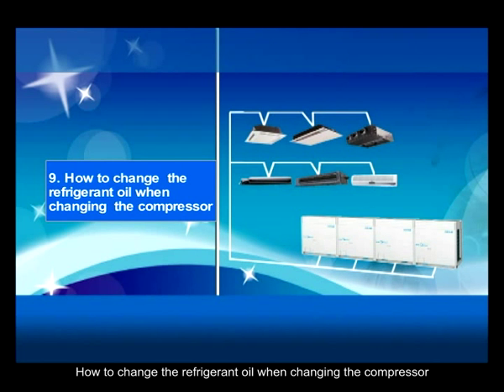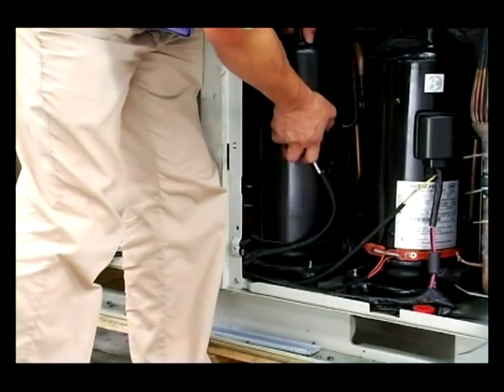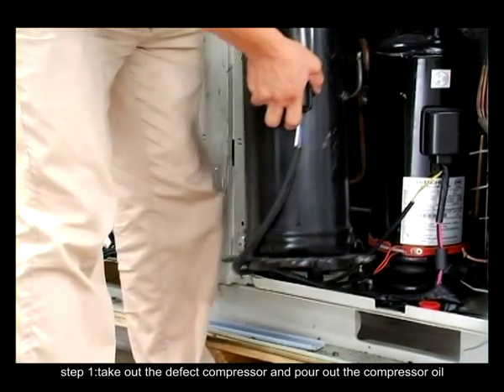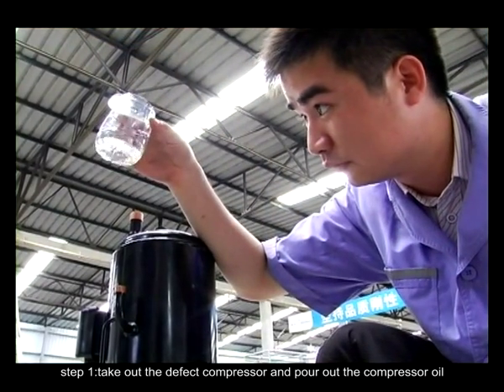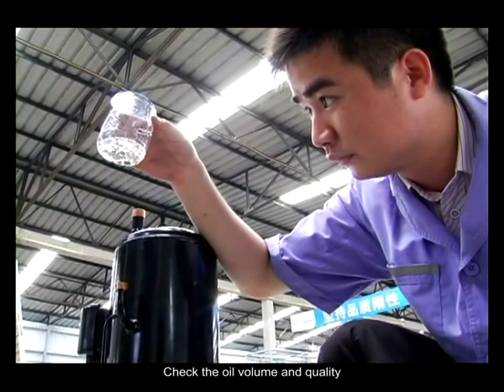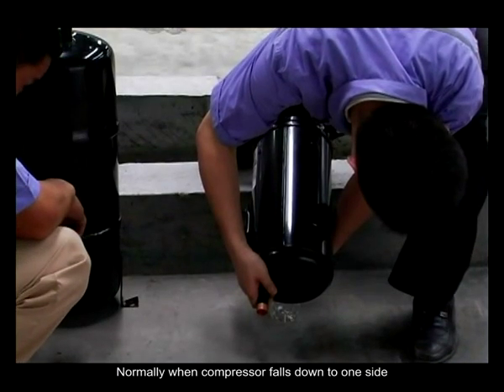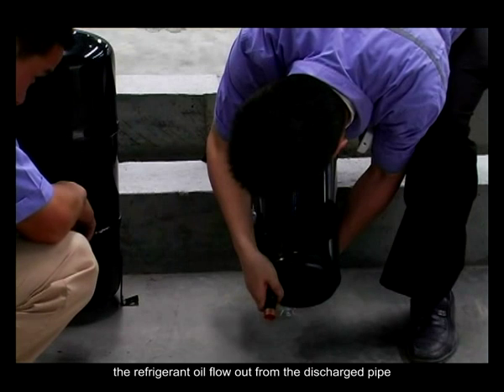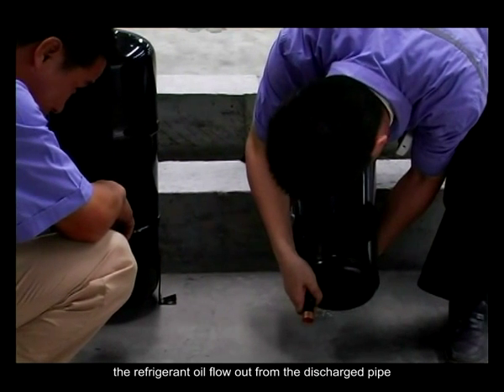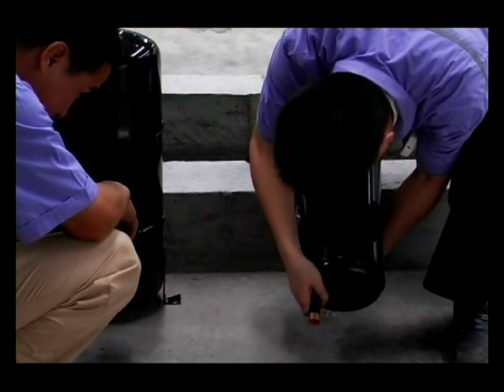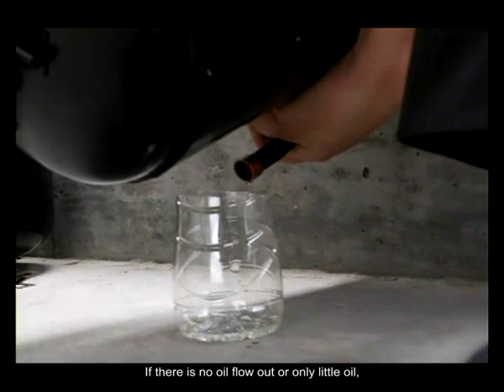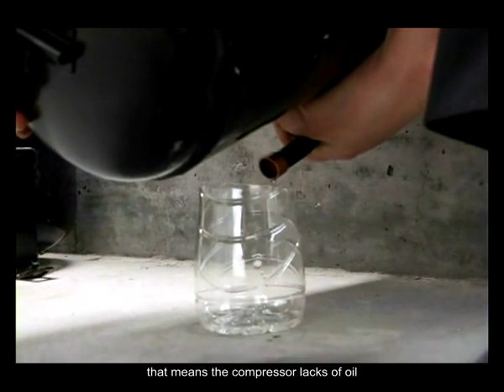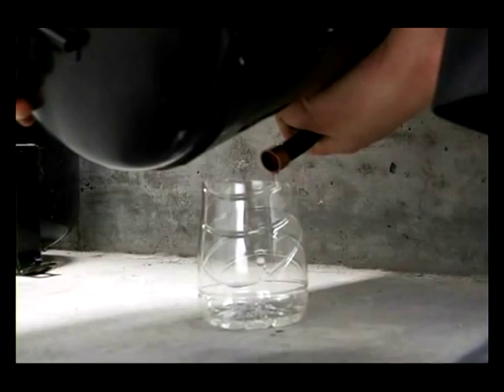How to change the refrigerant oil when changing the compressor. Step 1. Take out the defective compressor and pour out the compressor oil. Check the oil volume and quality. Normally, when the compressor is tilted to the other side, the refrigerant oil flows out from the discharge pipe. If no oil flows out or only a little, that means the compressor lacks oil.